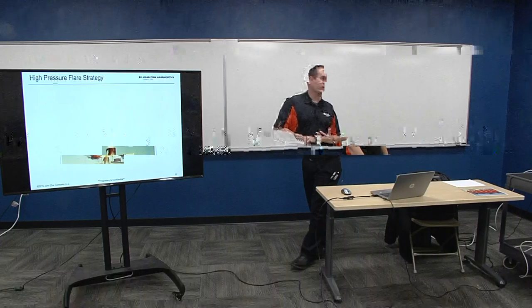So if you don't have air, you don't have steam, but you do have pressure in your line, you can go, again, unassisted, which is not that utility tip, but what we call pressure-assisted, right? It doesn't use any additional assist media, but it does use the internal pressure of your system, and it turns it into kinetic energy, right? So again, much like the steam in the steam jets is creating kinetic energy and pulling in that air, you can use the internal energy to create kinetic energy of the gas itself.